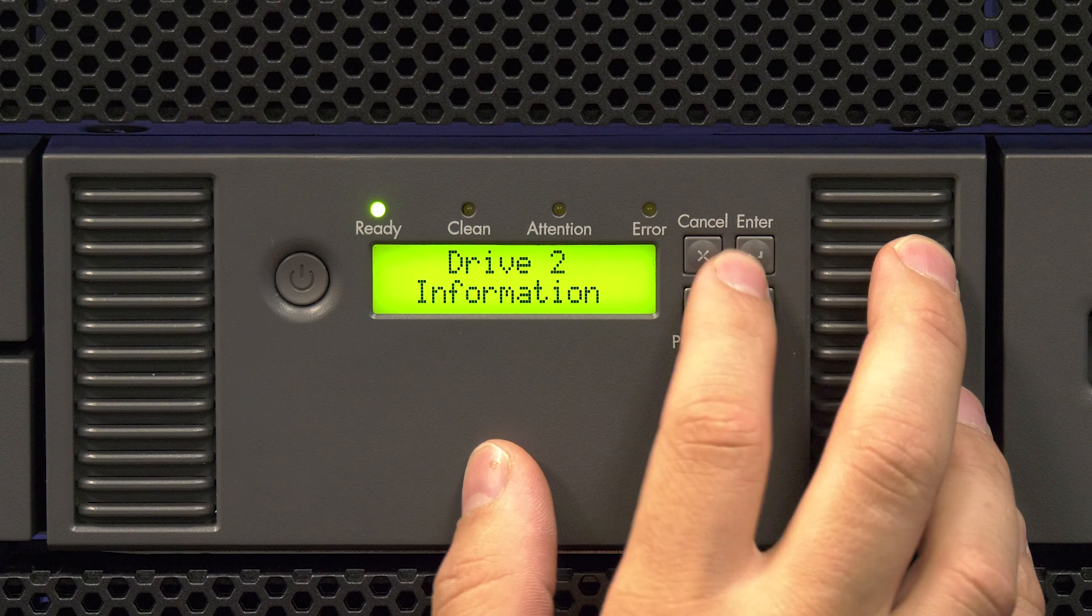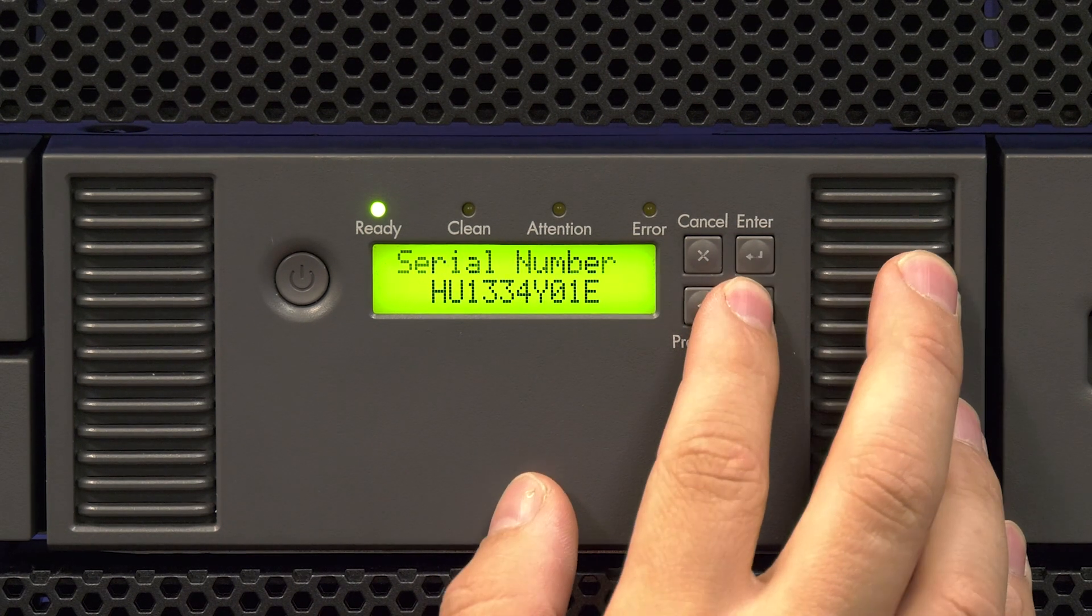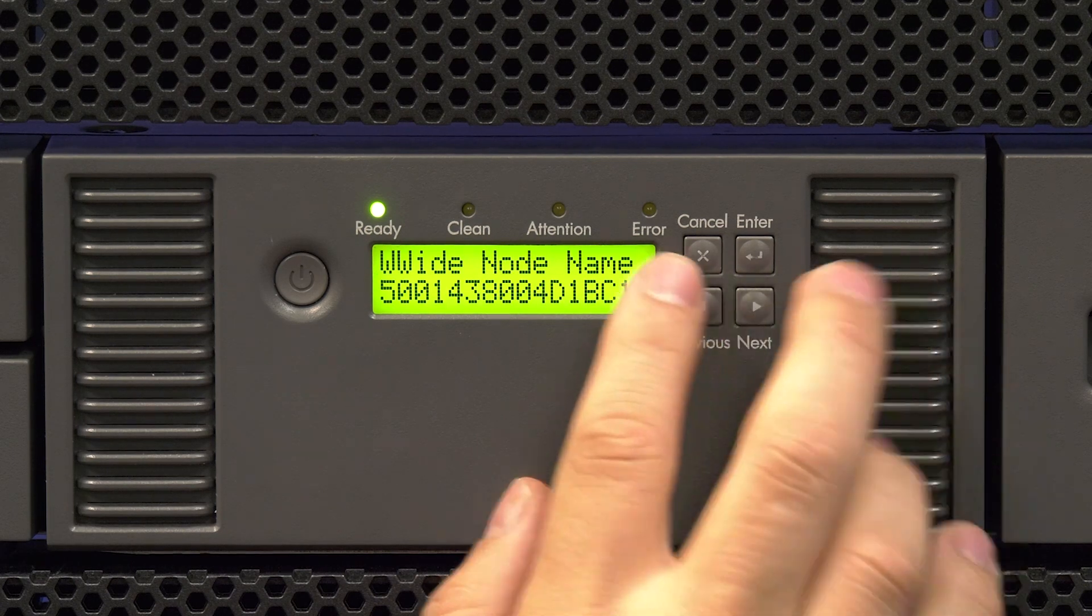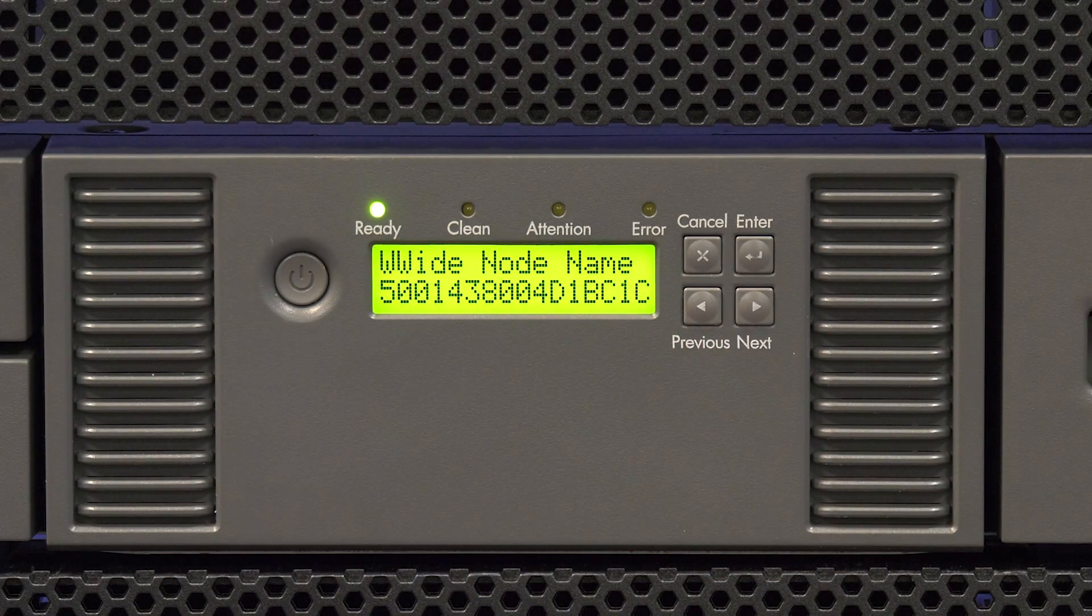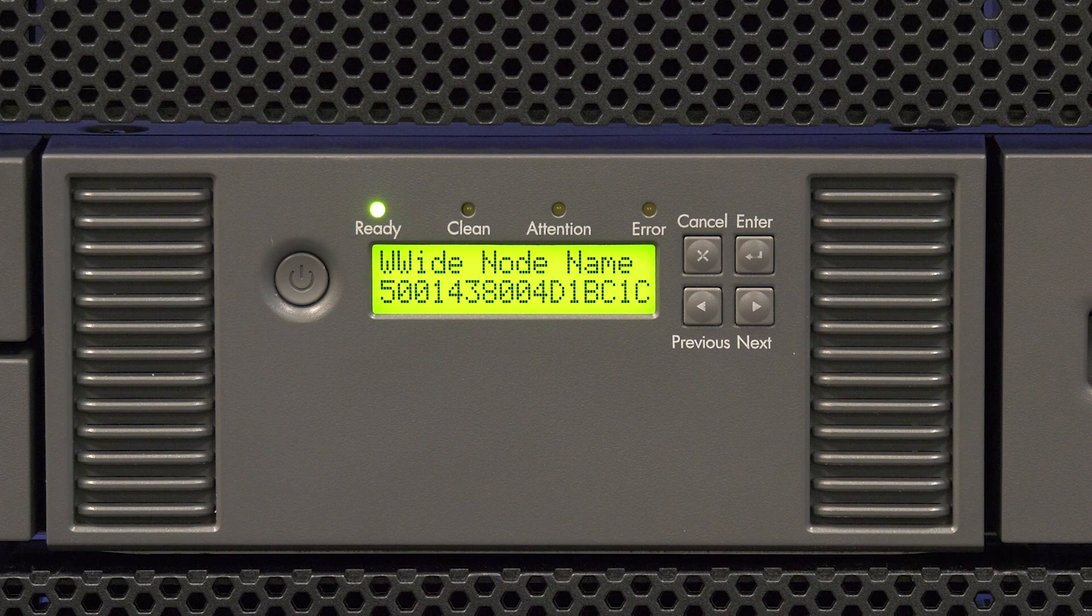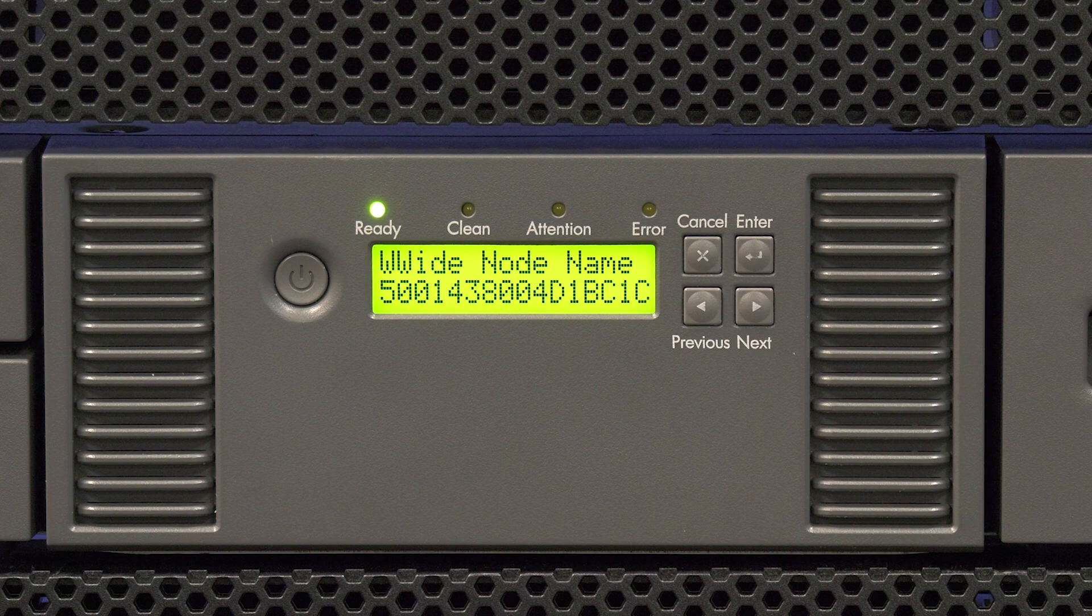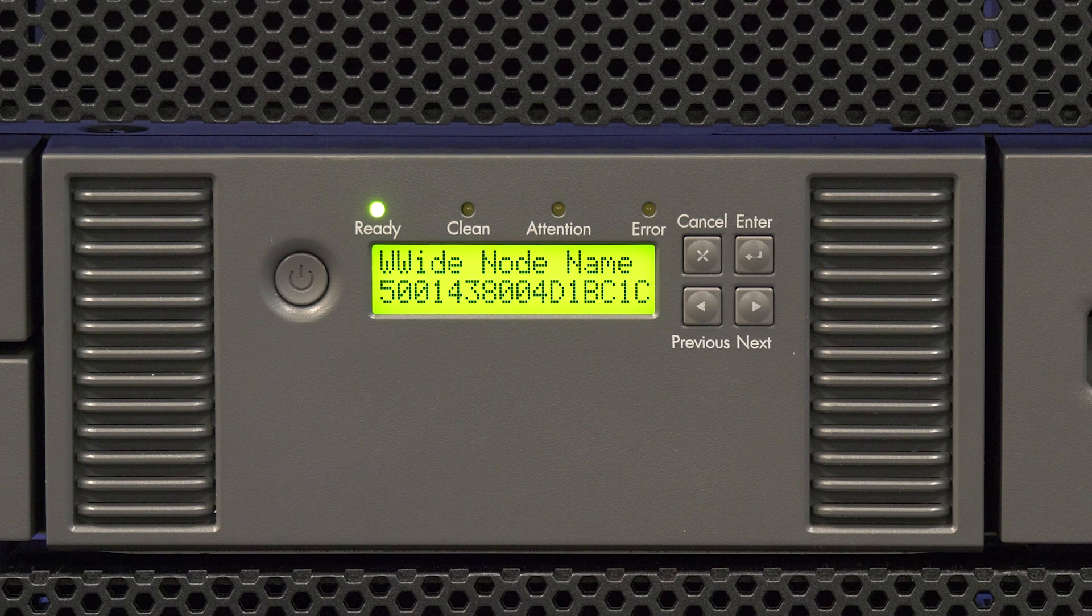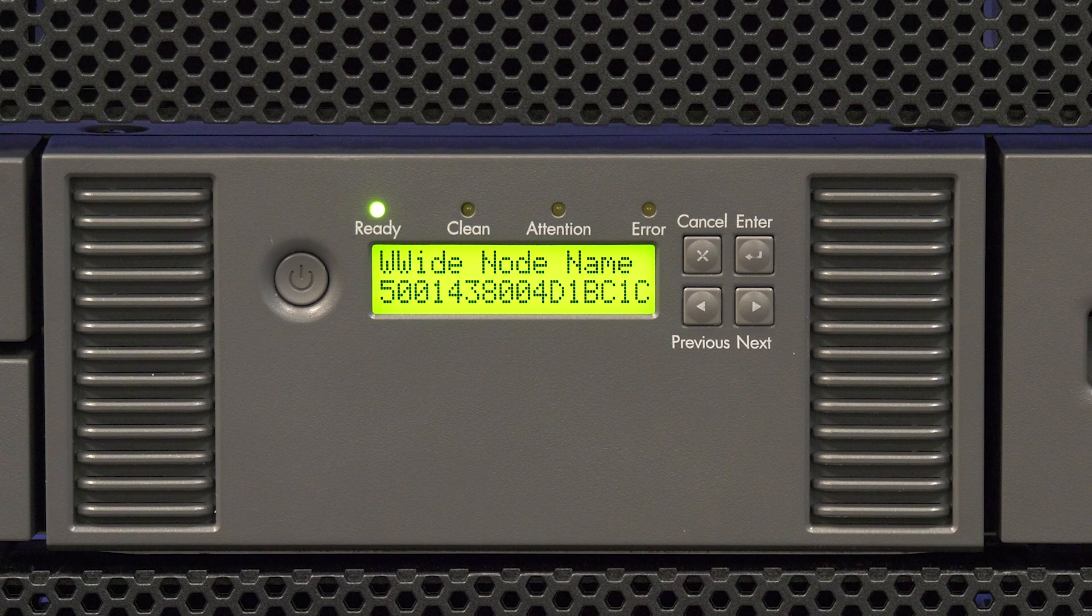Select the drive you replaced from the list and hit enter. Use the right or left arrows to scroll through the information for the drive until you get to the worldwide name. You will need to give both the original and replacement worldwide names to the person who administrates the fiber network if the drives go through a fiber switch before going to your host system. This way the administrator can update any zoning as needed.